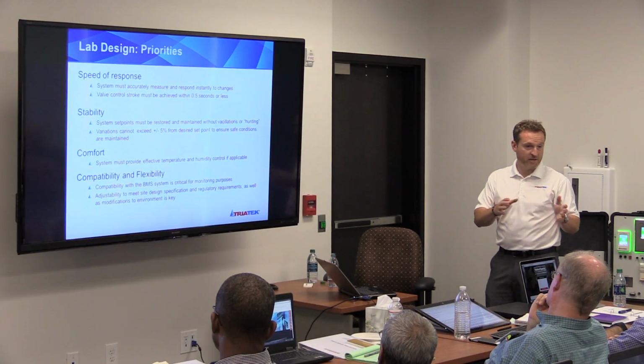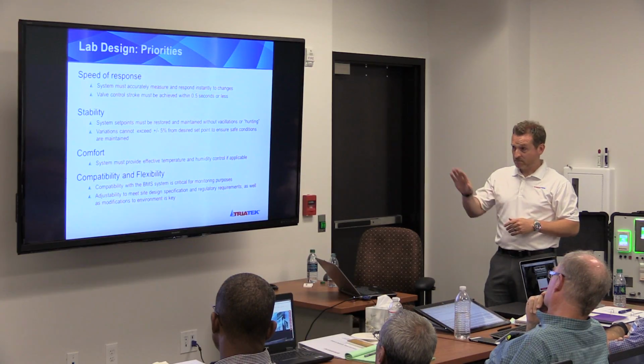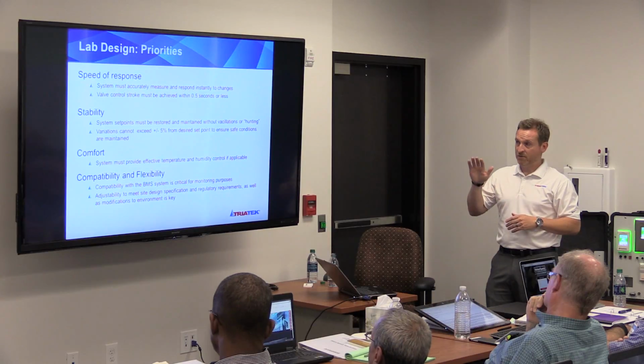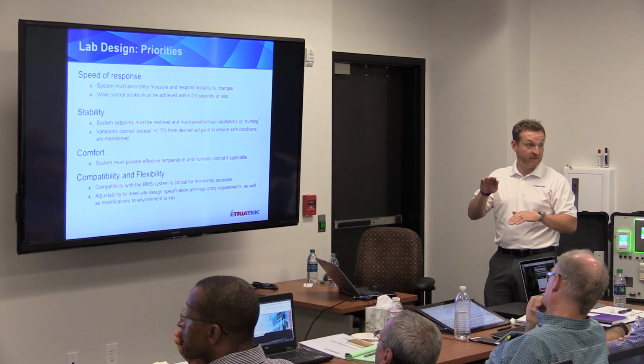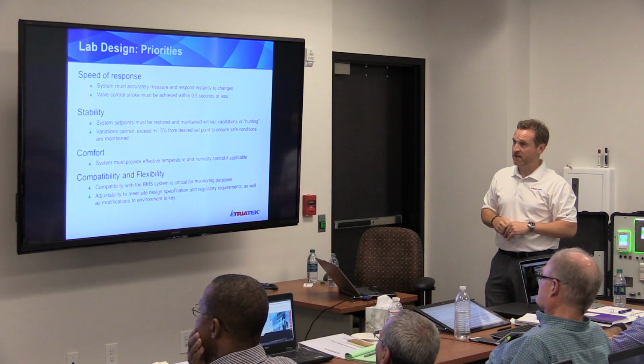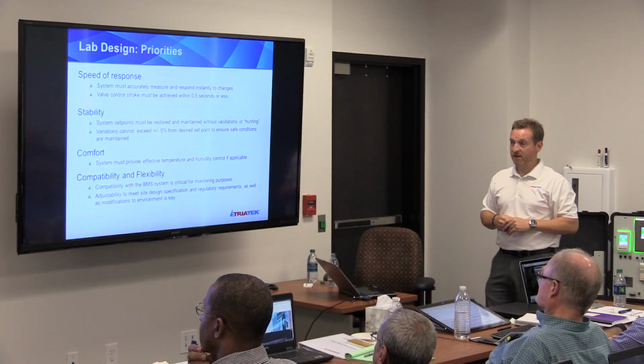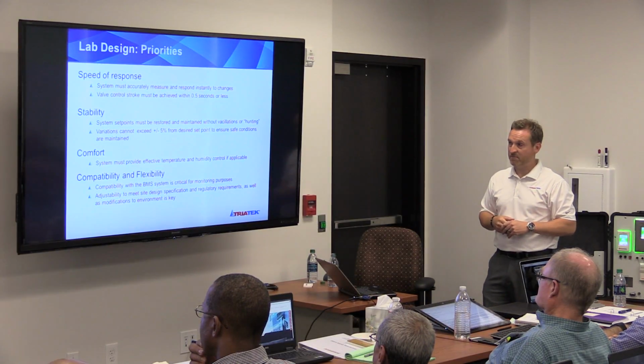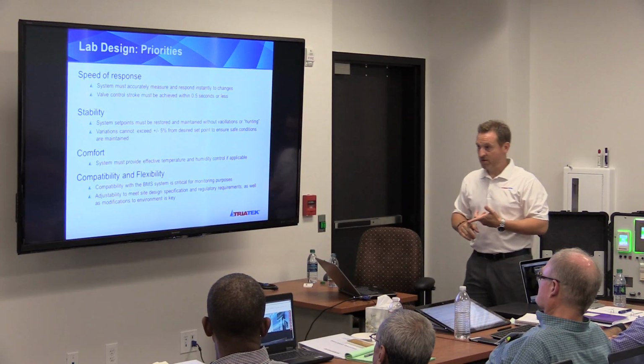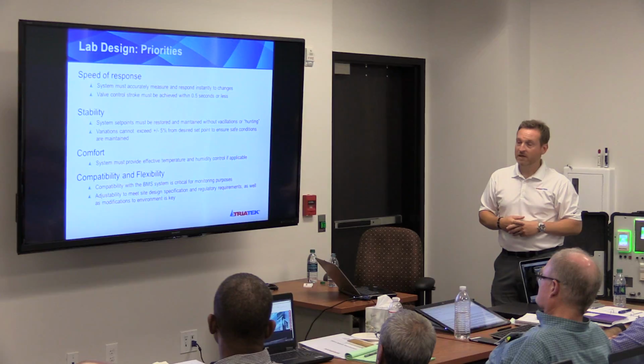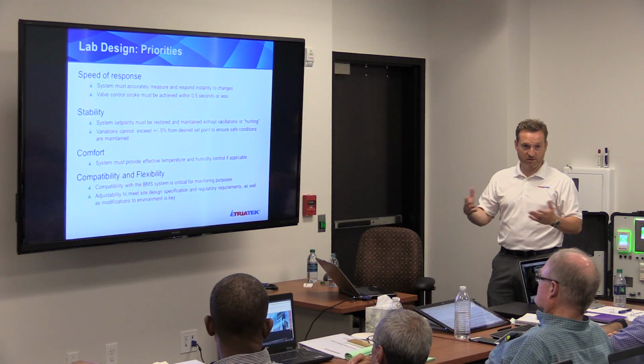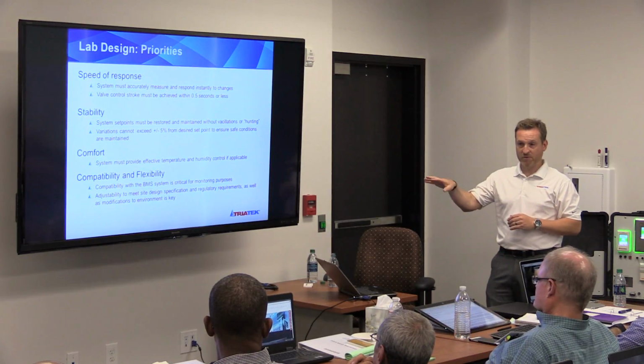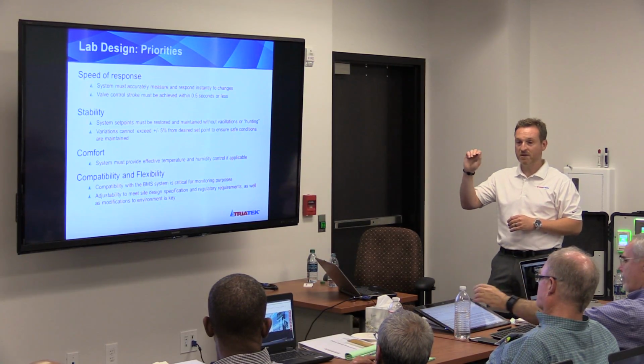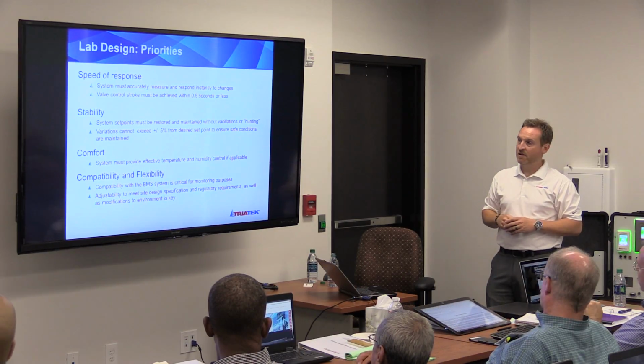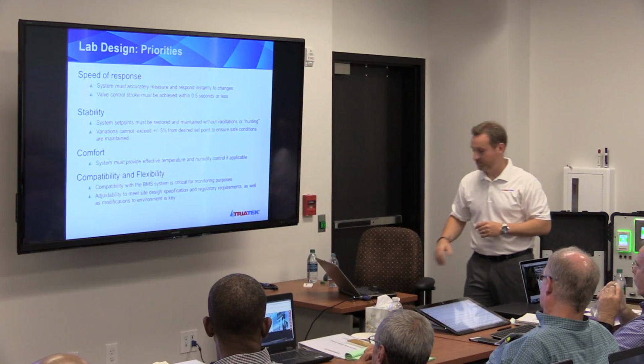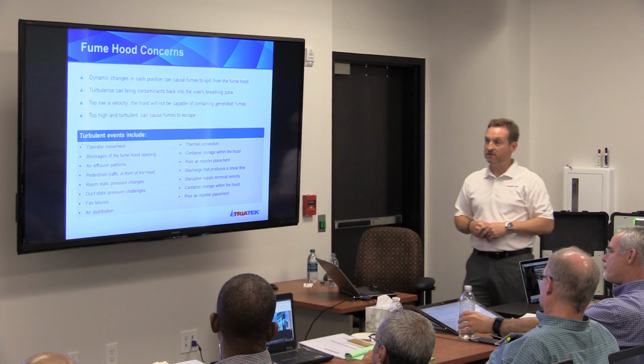A little different than a typical HVAC application. Stability, as I said before, we want to make sure that the room is stable. So we're doing this high-speed control without excessive overshoot or undershoot, so we minimize hunting. And then, of course, we want to make sure that we're maintaining a proper accuracy level, which is typically plus or minus 5% of CFM set point. Comfort is another, obviously temperature and humidity control if applicable. And then also compatibility with the BMS is critical. We want to make sure that the building management systems can read and write to these systems. We want to monitor alarms, change set points, whether it be temperature or airflow set points. All that can be done through our system from the BMS as well. Those points are definable, basically.